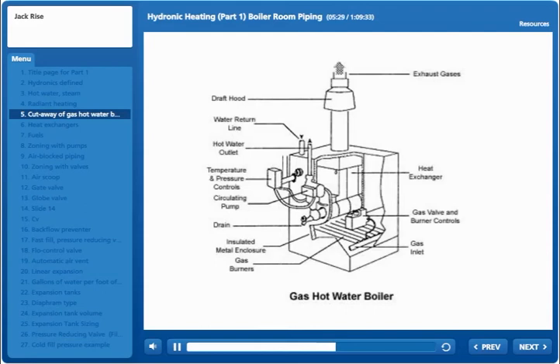Now, this is a barometric draft hood, and this is a barometrically drafted boiler. That means that the way the hot gases from the gas burner get out of the boiler is by buoyancy, the fact that they're hotter and less dense than the air that surrounds the boiler. All right, so they go up to the flue pipe that way. You can eliminate that draft hood, and you can have a fan there, and it could be fan assisted, which may or may not increase its efficiency depending on how the boiler was designed. Okay, but these are the basics. You're going to see that on any type of gas-fired hot water boiler you go to.